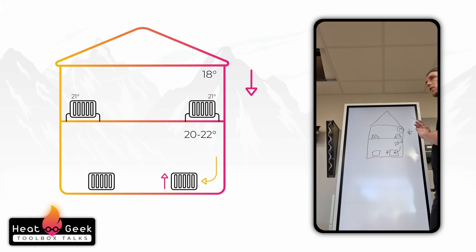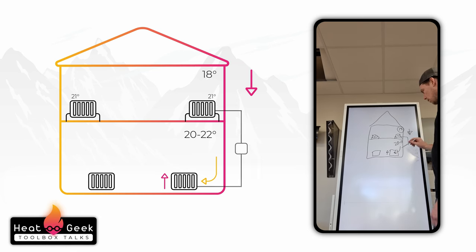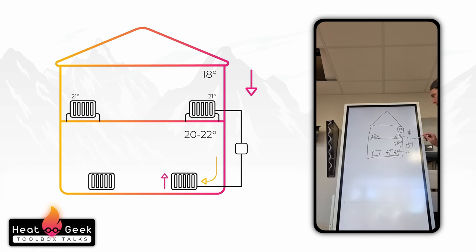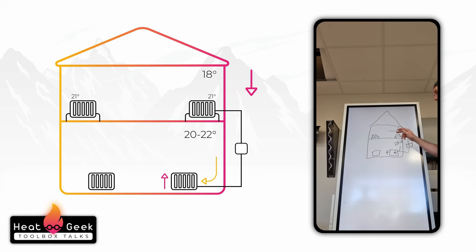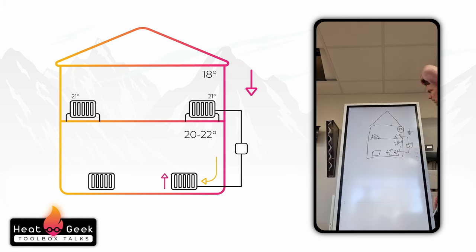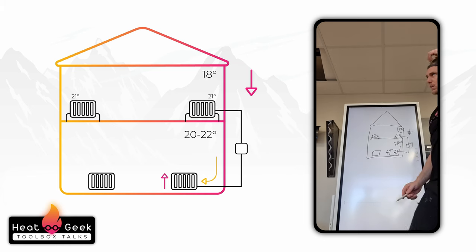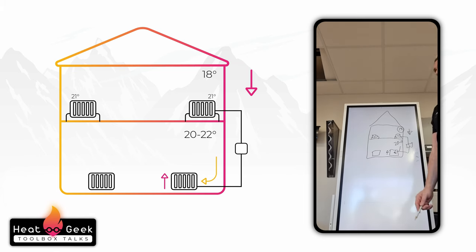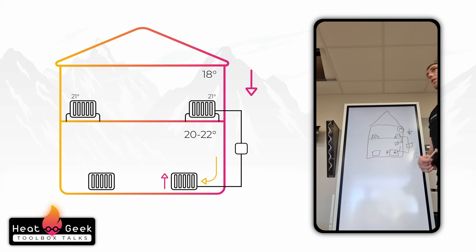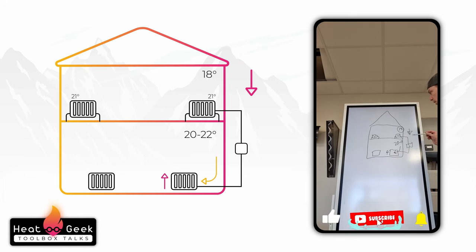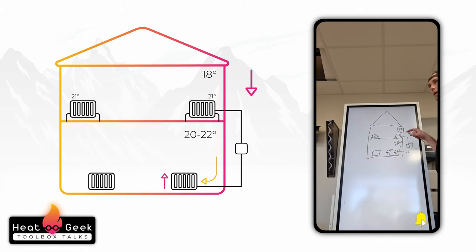I do kind of like the idea of zoning off with pipes all coming back to one central manifold. The reason being it's much easier to balance between floors and zones, so it self-balances a lot better, and you can isolate parts more simply. You'll be able to distribute the appropriate amount down that pipe and keep the velocity low. Whereas if you were trying to do the whole system in one circuit, then your velocity is much higher.